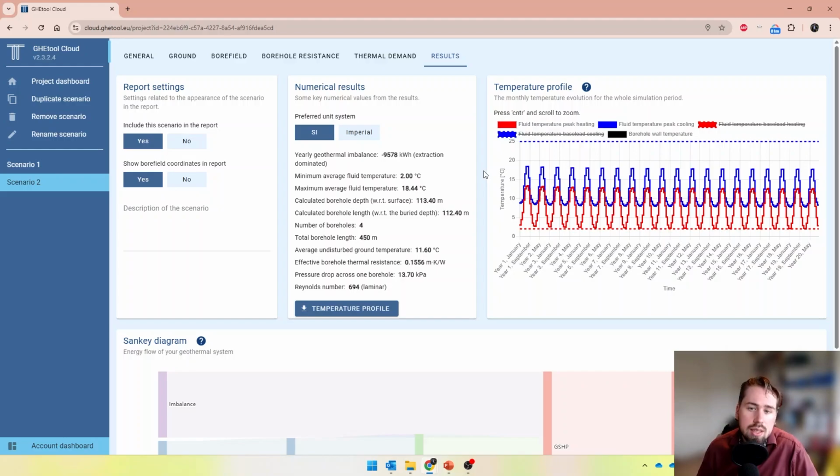So it's indeed above the threshold. So this is one solution. Just say, well, we increase the threshold for injection temperature during our cooling period. But of course, then you're not taking into account the summer comfort of your building, because you're saying, well, we do not care actually what the maximum temperature is.